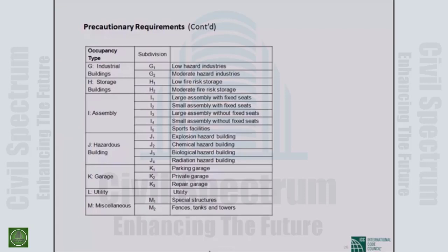So in that respect, when we give firefighting options for a garment factory, we always prefer, as per 2020, that it will be performance based, because there is a lot of variation of fuel quantity, hazardous ability, and a lot of that. So now as per 2020, garments is classified as G only. So you cannot directly say G2, but as it is not specified in BNBC 2020, you have to think a little bit differently. Some of the garments may be G2, some may not be. So you have to consider this.